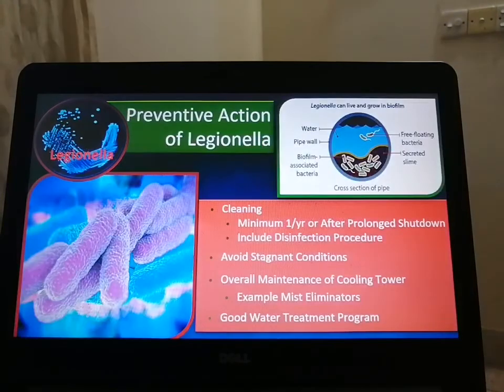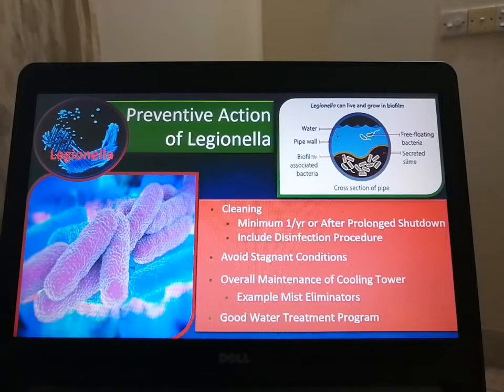If you see the preventive action regarding Legionella, like any other bacteria, if we can control total bacteria in any system, we can ensure, we can understand, we can feel that Legionella also will be controlled. But in any system, Legionella grows especially in the slime. If the system is heavily fouled, if you see a pipeline, normally the bottom side of the pipeline fouling grows. So basically Legionella grows inside the slime and inside the fouling. If there is no fouling, Legionella cannot reproduce, cannot grow in number or mass. Even if Legionella is present, their number will be very low, and that will not create a problem unless its number becomes very high.